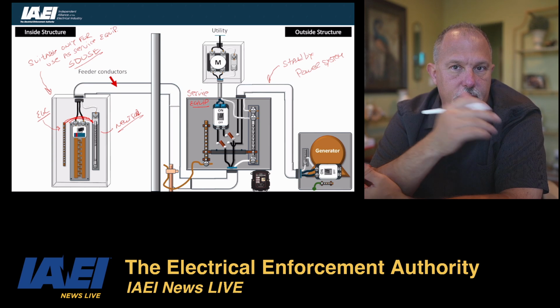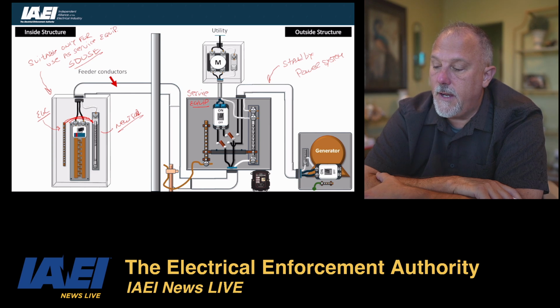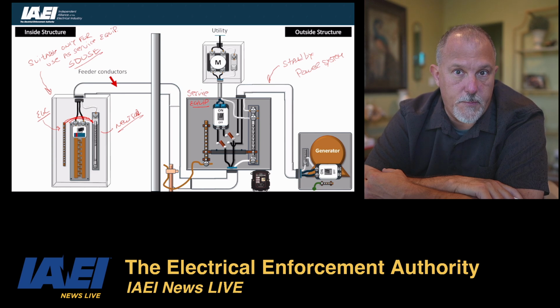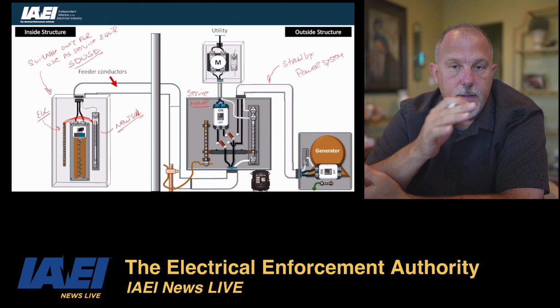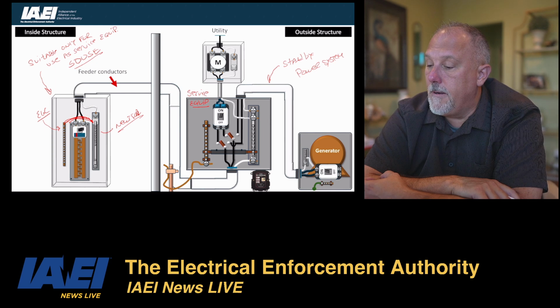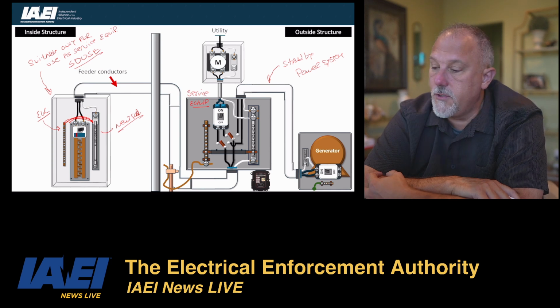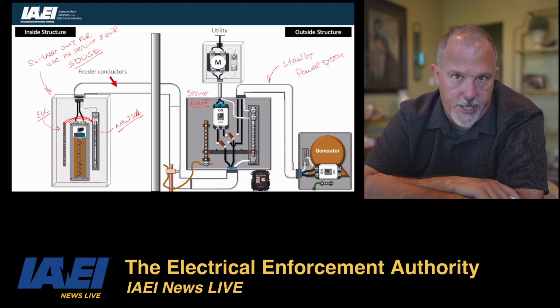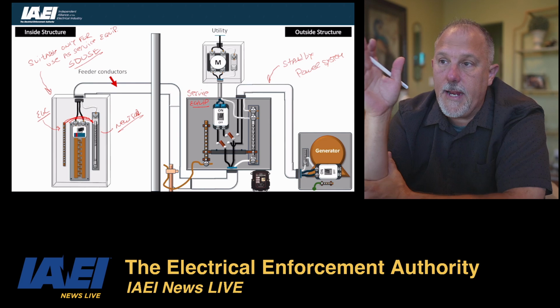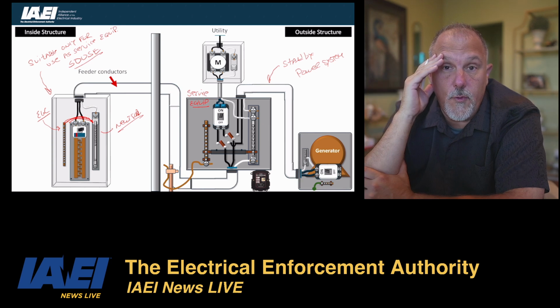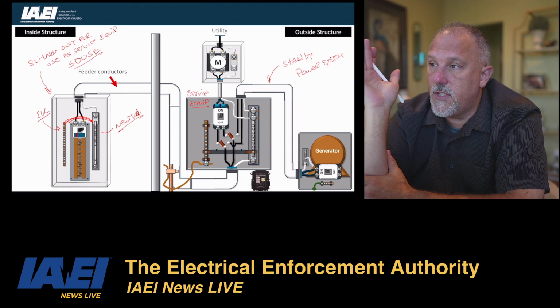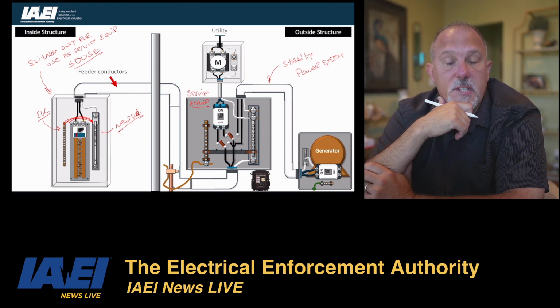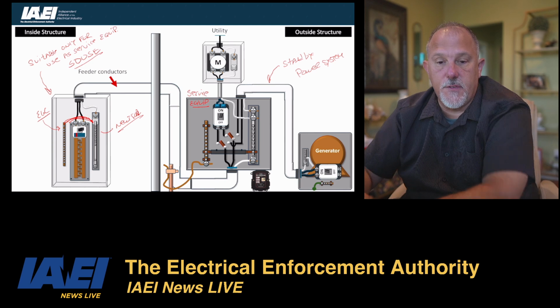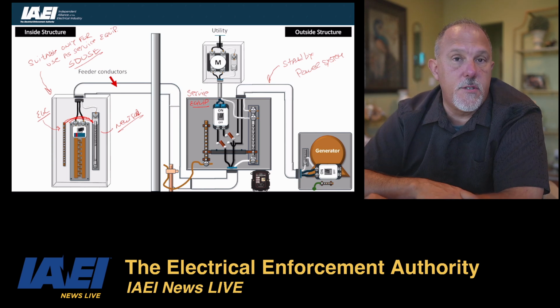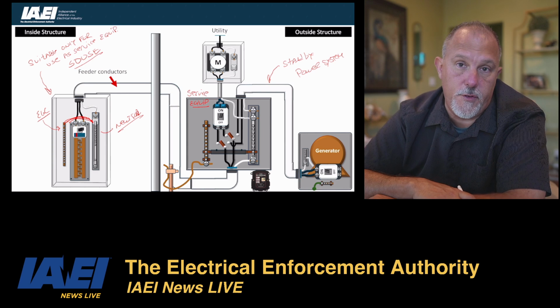Now, I think on the chat from last week, there were a couple comments that said that they have installed many service panel boards where the bonding can be converted, so it would be SUSE rated: suitable for use, not suitable only for use. So you'll have to check. Now, because of the language in 230.82(5) that basically says if you are going to supply these standby circuits for standby power systems, that it has to be service equipment, then you're going to buy a transfer switch that's service rated. It could be suitable for use as service equipment. It could be suitable only for use as service equipment.